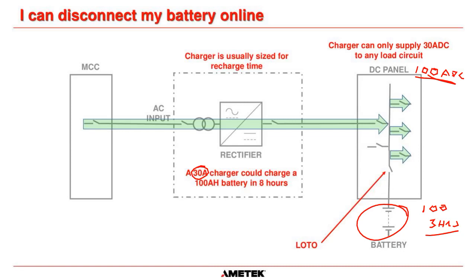But what you've got to understand is that when you put the battery back on charge, the battery will go back to doing 70 amps in the battery. I see what you're saying. We'll do 30 amps. So a good design engineer, you are correct, should rate this at 130 amps. But the issue that we always have is that the DC panel is never ever going to have 100% load on it. That's just for design specs. But I do see your point, John, and my apologies if I misled you earlier.